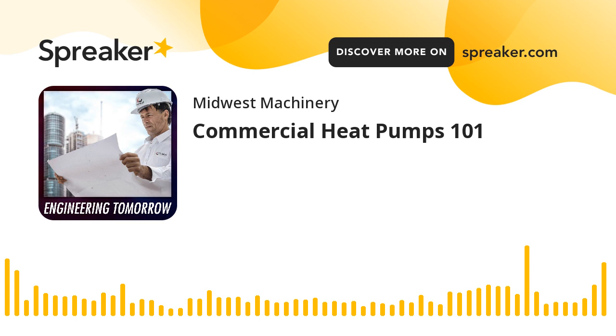If it can't make the duty, you just bump it up one size. The savings comes from the materials and labor of running that second pipe. So by eliminating that, you're cutting back on a lot of upfront cost. Your main loop pumps are also getting smaller because you don't have to overcome the head pressure of all the heat pumps. Every heat pump will now have its own little itty-bitty circulator that will pump the water through the heat pump and back to the loop.